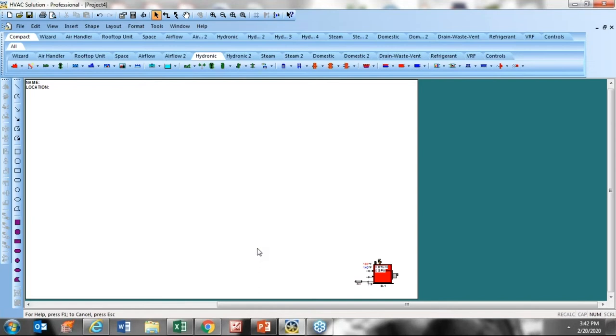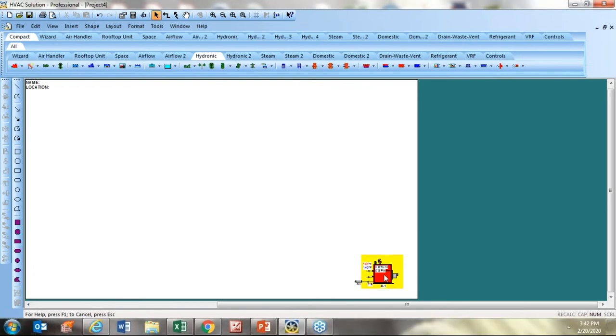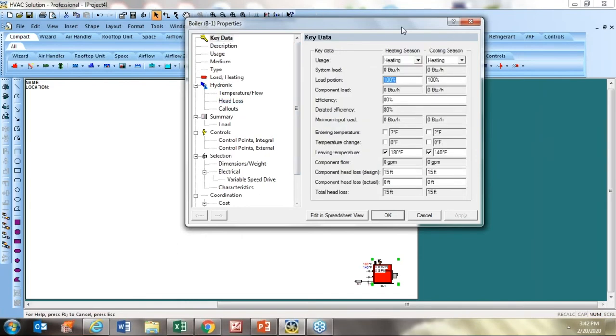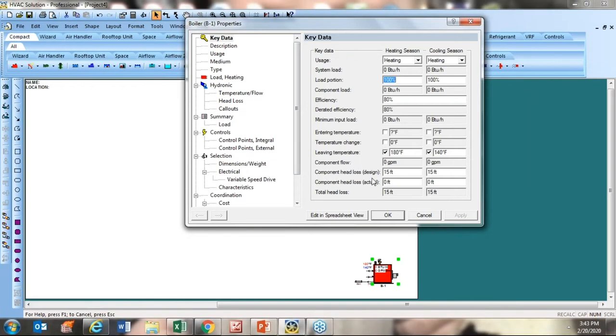One of the most important things with the software is access to the information associated with each component. Every component on the screen — including the drawing itself — has a property box. If I double-left-click on the boiler and click the Key Data tab, you get a feel for what these property boxes look like. They have a lot of information, with spreadsheets and formulas behind the scenes. Here's our first example of a default value — the component head loss shows 15 feet of pressure drop through that boiler.